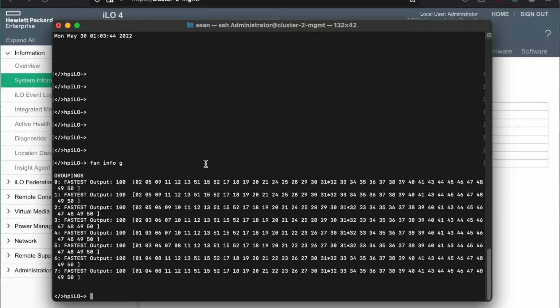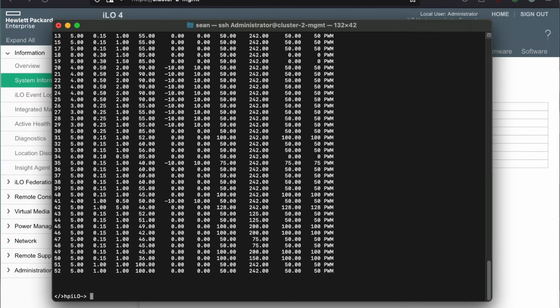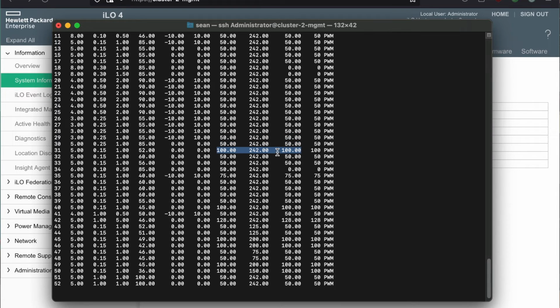So once you've worked out which sensor is making the fans run faster, and in this case every single fan is reading 31, so 31 is the problem sensor right now, you run fan info g. And that shows us a list of all the different sensors. Here's 31, that's the one that's causing us problems. Now there's a lot of data here, but honestly the only things you really need to pay attention to are this column and this column.